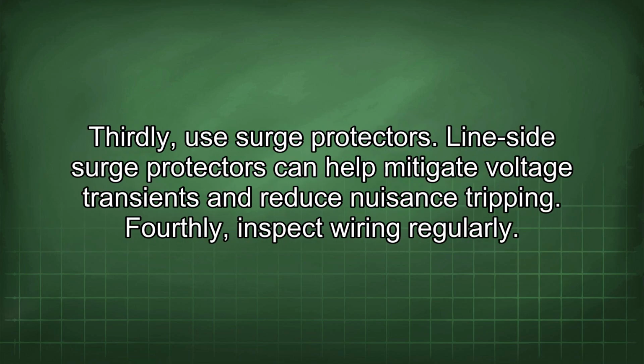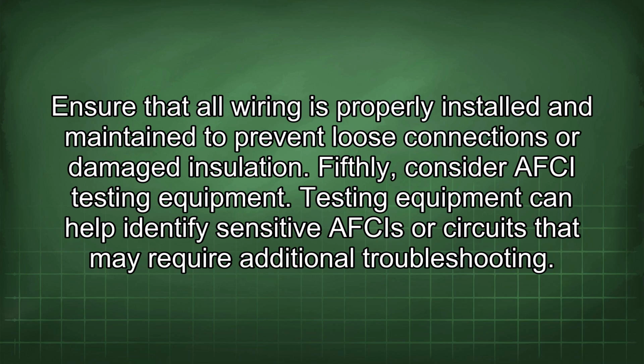Thirdly, use surge protectors. Line-side surge protectors can help mitigate voltage transients and reduce nuisance tripping. Fourthly, inspect wiring regularly. Ensure that all wiring is properly installed and maintained to prevent loose connections or damaged insulation. Fifthly, consider AFCI testing equipment. Testing equipment can help identify sensitive AFCIs or circuits that may require additional troubleshooting.